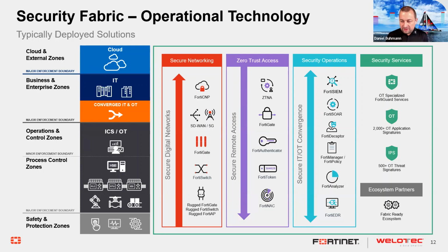With this firewall, you cannot just do firewall features. You can also extend your network on a layer 2 basis if you have to route some layer 2 protocols like Goose, or maybe you want to set up an SD-WAN for OT. It's not just an IT feature where you interconnect your business locations. You can also use SD-WAN for OT and make sure you have different connections like MPLS, DSL or 4G, 5G, whatever you want to use, to make sure your control system data, your process, is always running. Because if one of these connections shuts down or crashes, you can make sure the OT data is rerouted through a different connection. If DSL or MPLS goes down, you can use 5G to forward the data and make sure it reaches the control room.